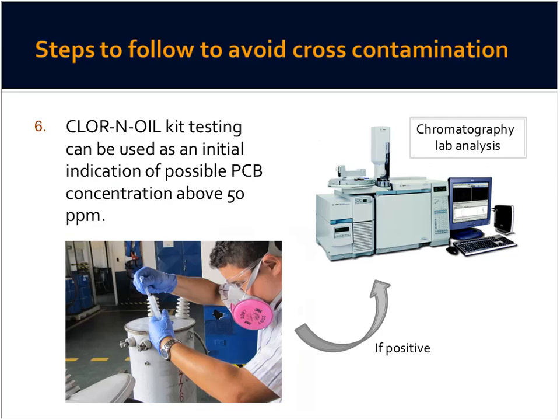The first initial step to testing should be, or the least expensive one at this point, and it works as an initial screening, is the CLOR-N-OIL kit. It can be used to determine whether or not there's a concentration above 50 parts per million. This kit will not tell you what concentration you have if you do have PCB concentration. It'll tell you if it's above 50 parts per million.